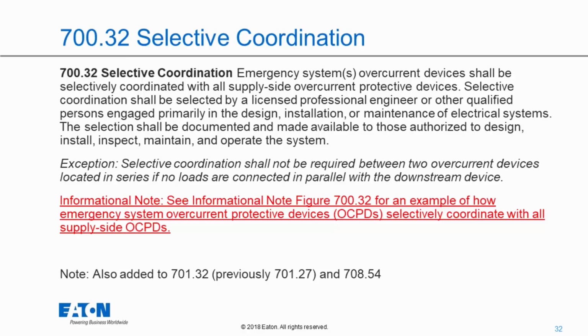In the public input stage, we resolved his public input saying that the text is clear. It says that the emergency system overcurrent devices shall be selectively coordinated with all supply side overcurrent devices. All means all. So whether it's a normal supply side device or an emergency supply side device, selective coordination is required. In the public comment stage, we decided that although we don't want to change the wording in the parent text, we do think there might be some benefits to adding an informational note and a figure, and that's what we did here in the 2020 edition of the NEC.